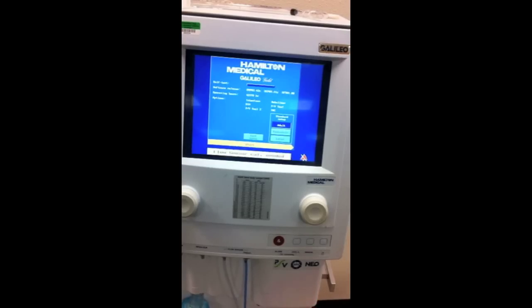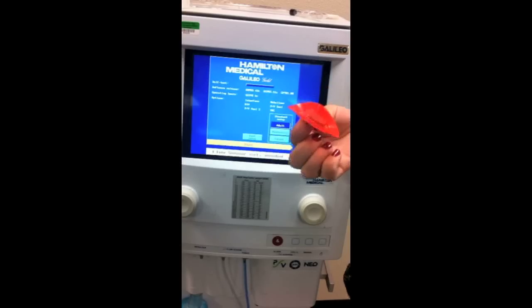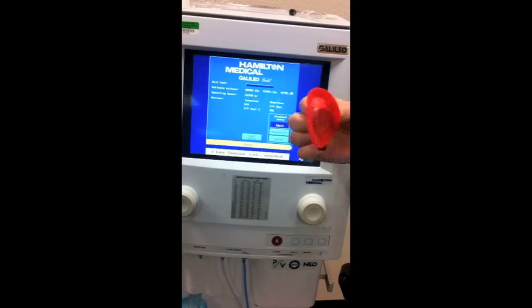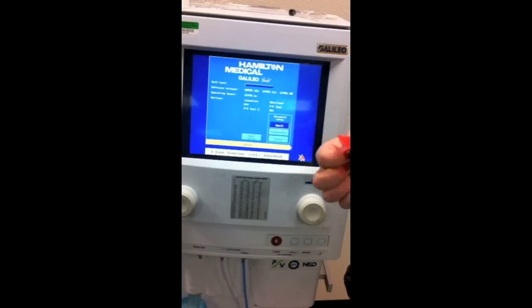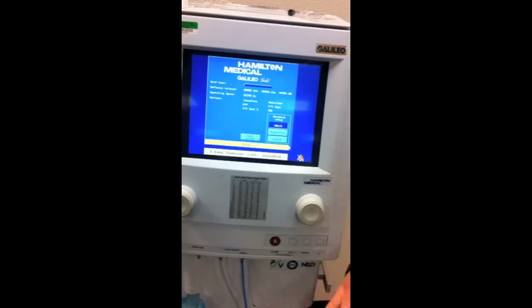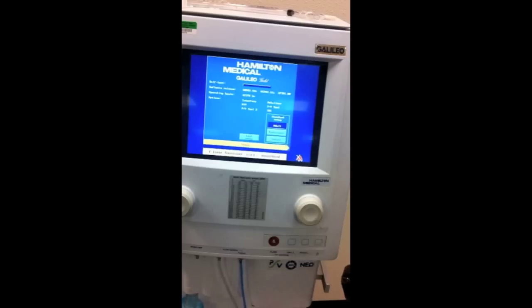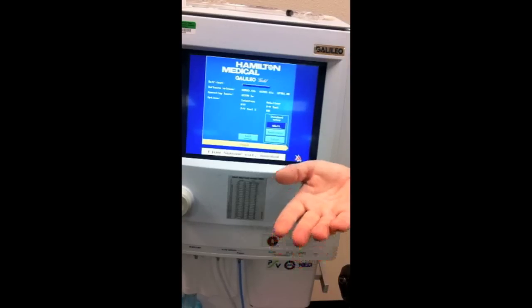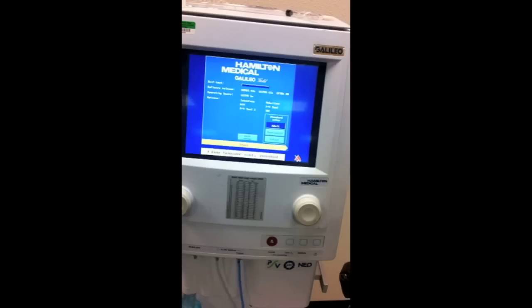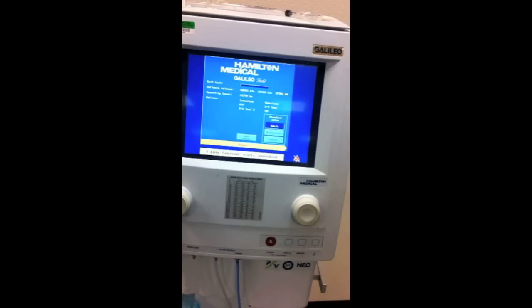This twists and comes out and has the diaphragm in here. You must be aware of this with this ventilator because if this is in wrong or it sticks or anything like that, it won't work because it won't cycle in between inhalation and exhalation. It has a little magnet in it. It literally goes up like that during inspiration and goes down during exhalation to allow that to go on. Every ventilator has an exhalation valve. It's just a matter if you can see it on the outside or whether it's on the inside.